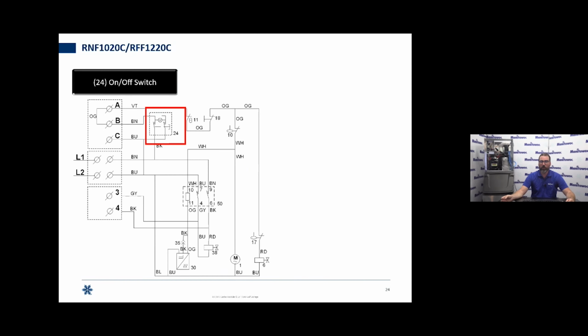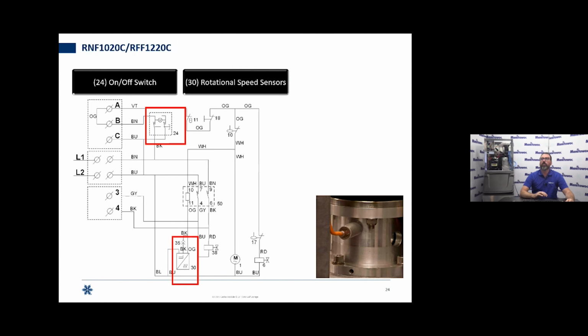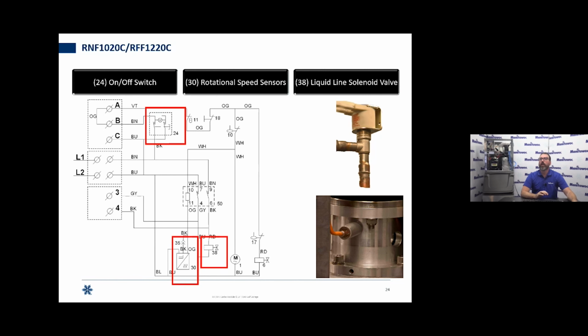I mentioned earlier that some of our larger machines, although they still use a rotation sensor, do so in a different way. As you can see in this wiring diagram, we have our L1 and L2 coming in. So that's going straight down to what would be the liquid line relay, control relay coil. So it's controlling a relay that's controlling the liquid line solenoid. When we open up that liquid line solenoid, what that should do in the remote condensing unit is bring refrigerant flow up to it and close our low pressure safety switch. At that time, we should start the condensing unit up and we should be making ice at that point.